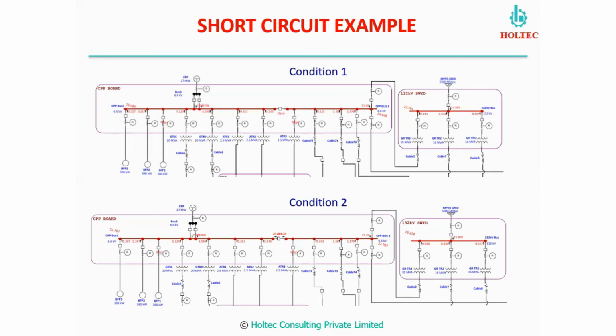When we close the bus coupler, which means we are making the CPP and grid run in parallel, what is happening? The fault levels on both sides of the buses have increased substantially. It becomes 52 kiloampere on the CPP bus, against the rating of 40 kiloampere. So it is not advisable to operate without preventive measures or preventive action to take care of these high short circuit currents in the system.